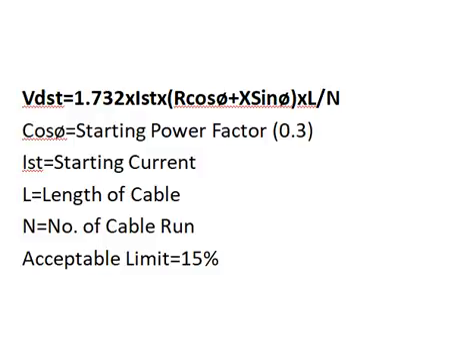The starting current depends on the motor starter type — whether it is direct online starting, soft starting, or VFD starting. If it is direct online starting, the starting current is generally six times the continuous full load current rating, and with a 20 percent margin, it becomes 7.2 times the rated full load current. The cosφ power factor used here is the starting power factor, which is typically 0.3.